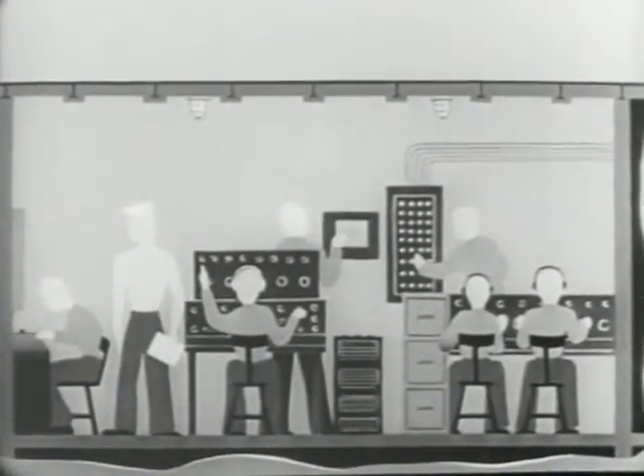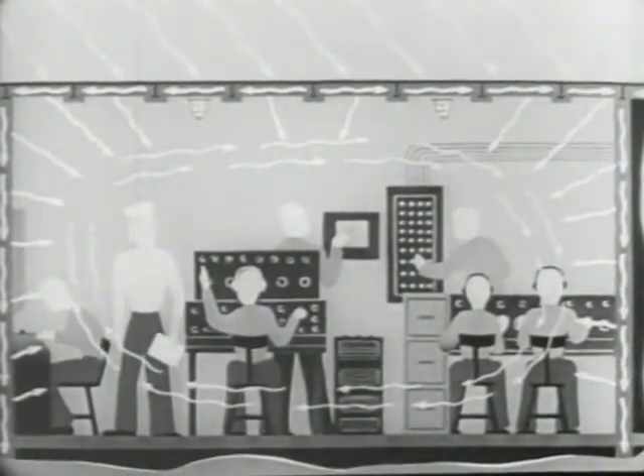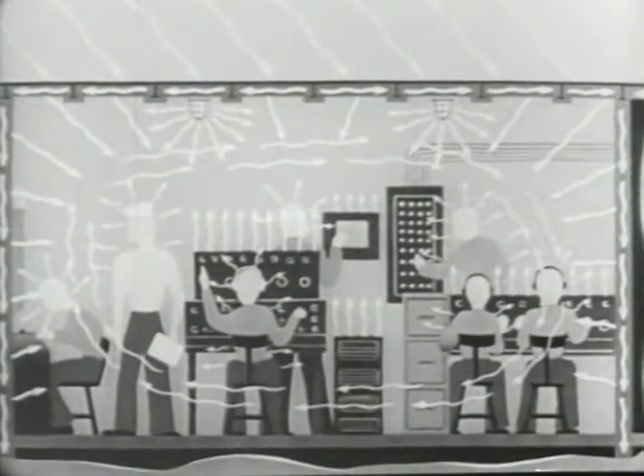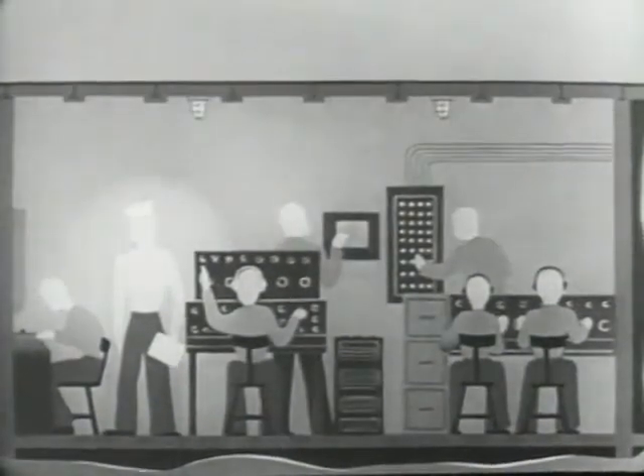Let us consider a typical space immediately below a weather deck. One of the things influencing living conditions in such a space is radiant heat from the sun. Some of this heat radiates directly to the space, and some is picked up by air currents within the space. Additional heat is produced by electronic equipment, by electric lights, and by the bodies of the crew. As heat and moisture within a space accumulate, the temperature and humidity rise rapidly. Unless adequately taken care of, these conditions will adversely affect personnel.